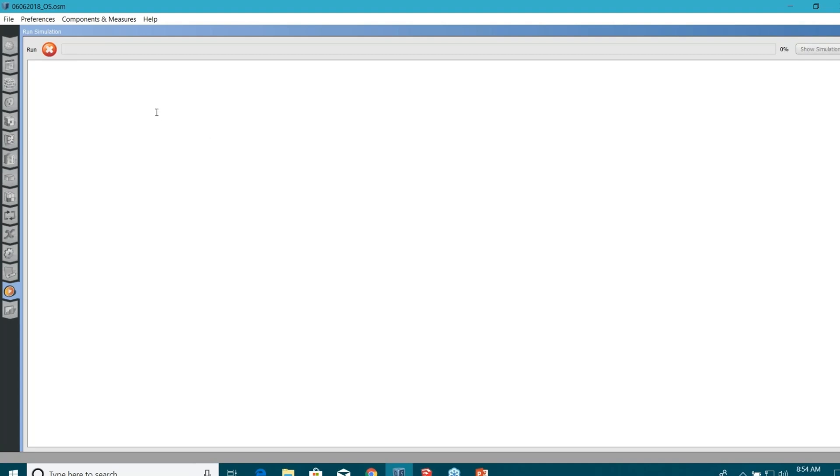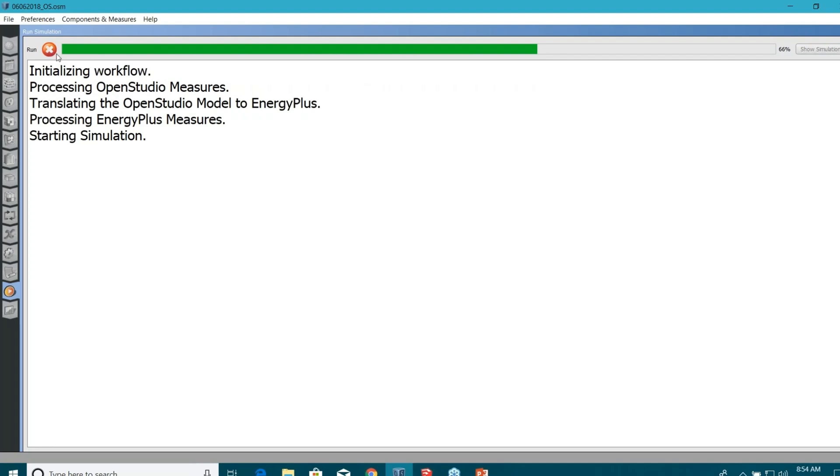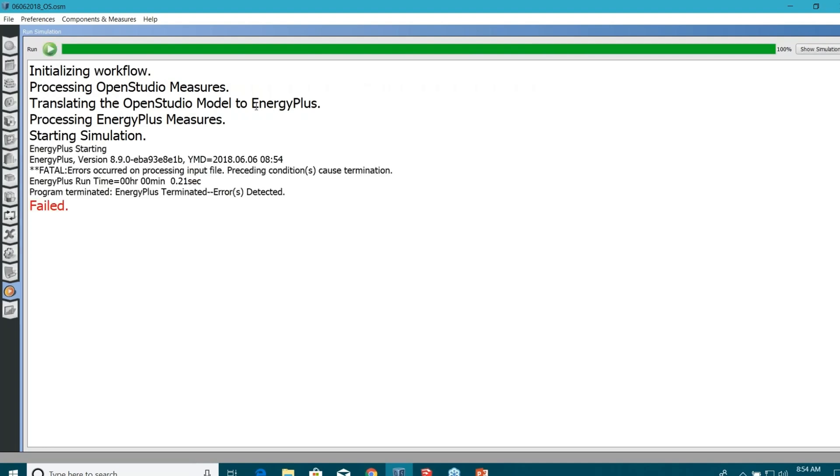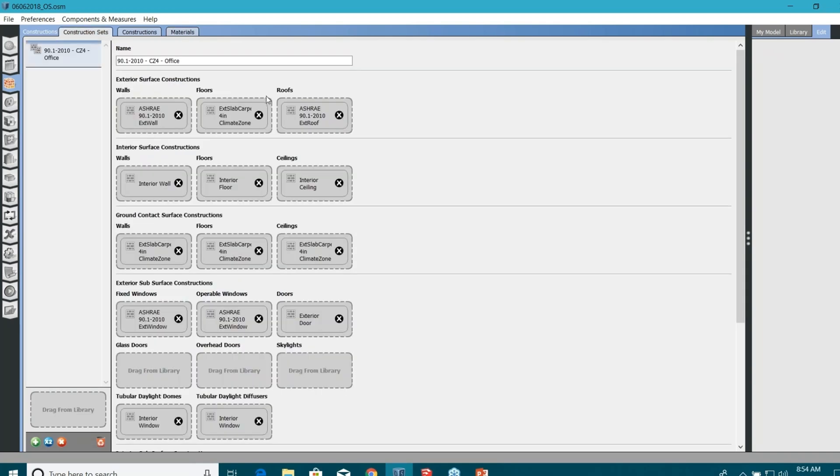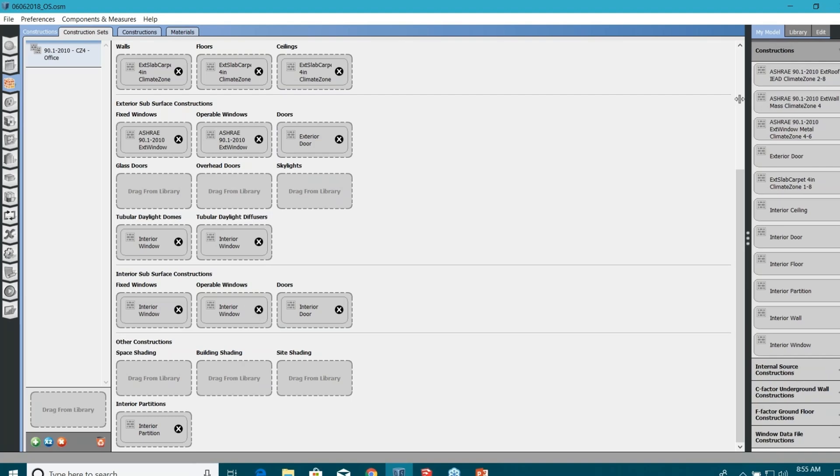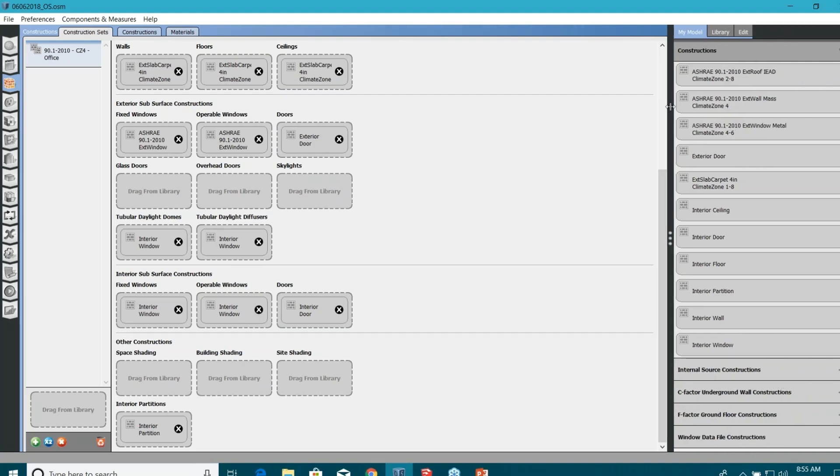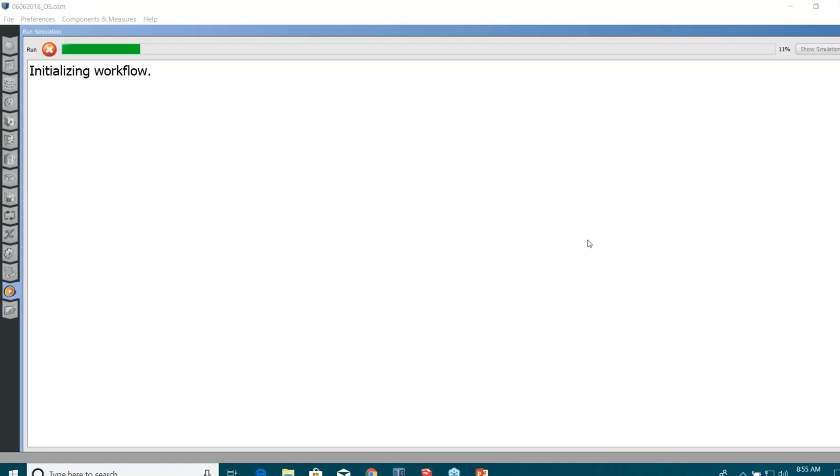Once you are fine with each and every tab, run the simulation. It might give me some errors because I have skylights and in OpenStudio it doesn't bring you properties for skylight. It will definitely crash. So I already clicked run, so I don't want to stop it in between. It's just gonna crash maybe in the next five or ten seconds. I'll be fine. So it crashed on me, I knew it. I'm just going to provide the properties for my construction set. I need to provide properties for my skylight. You can see there's nothing in here. That's why it crashed on me. What I'm going to do, I'm just going to provide some properties here to just run the simulation, maybe like a stair window for now. And then run the simulation one more time. I hope it works this time.